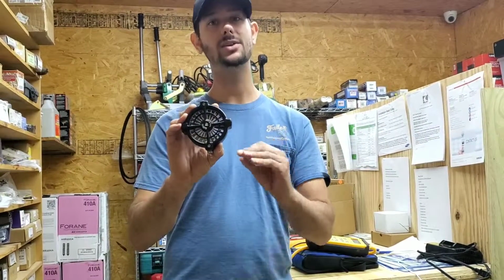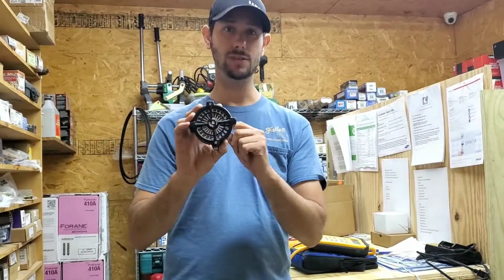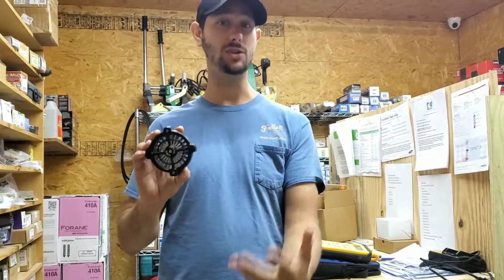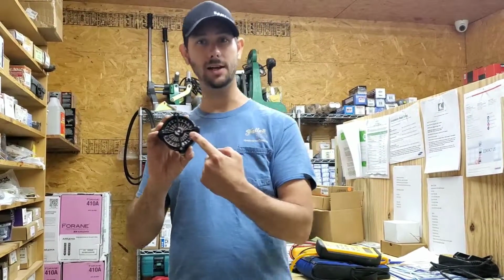Why do you have to do that? Because there's a formula that you can use after you get all your measurements, and it'll tell you the BTU output of the unit, and it'll tell you the CFM. So if I have a 3-ton unit that requires 400 CFM per ton and it's 1200 CFM, I'll be able to know that from using an anemometer, guys.